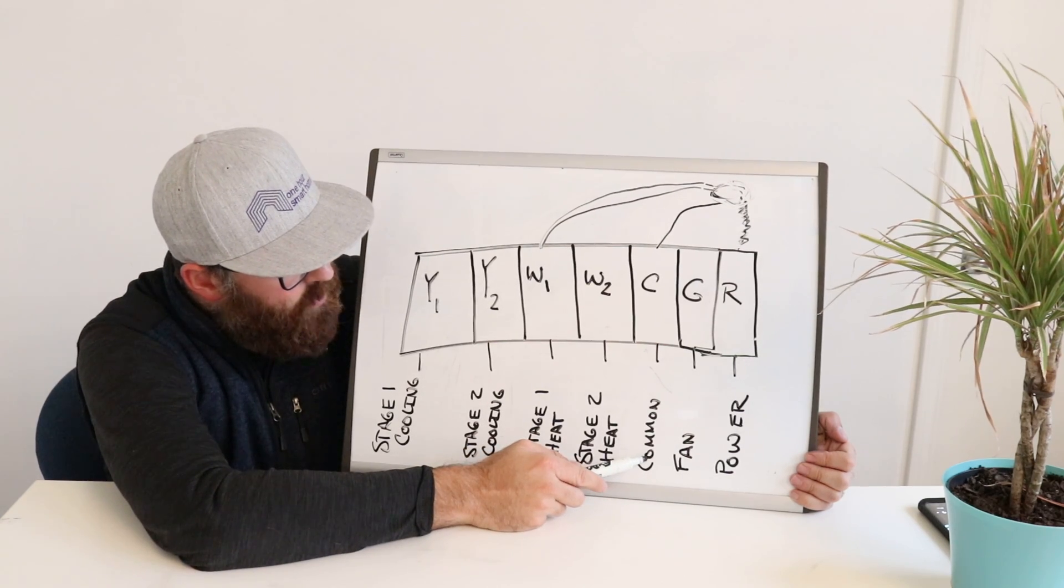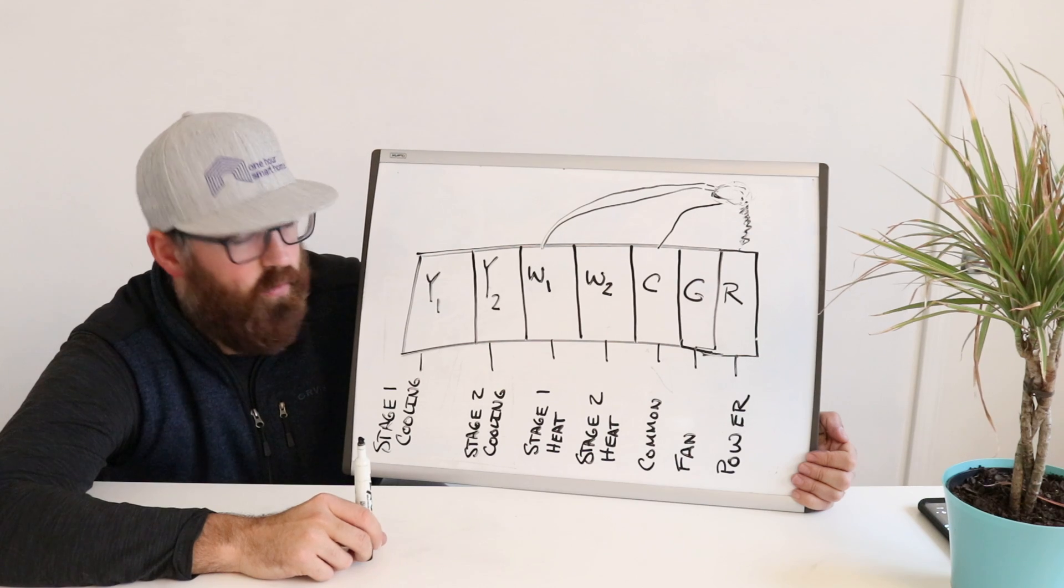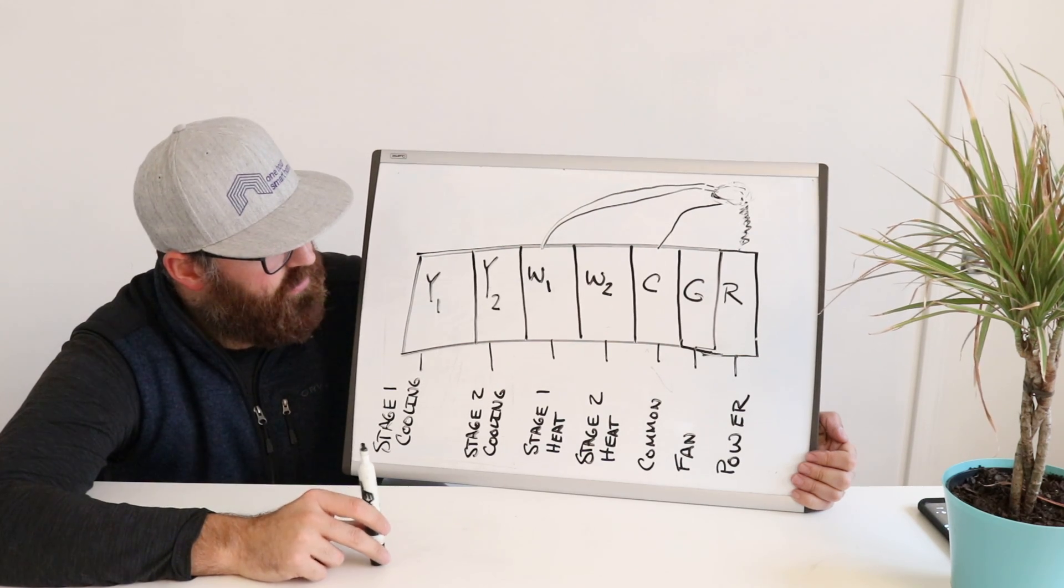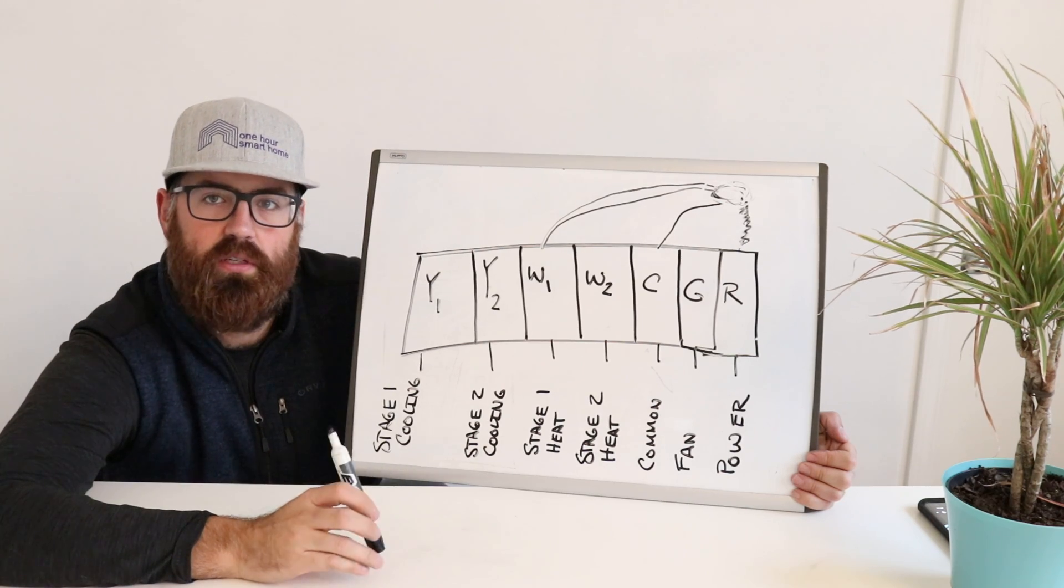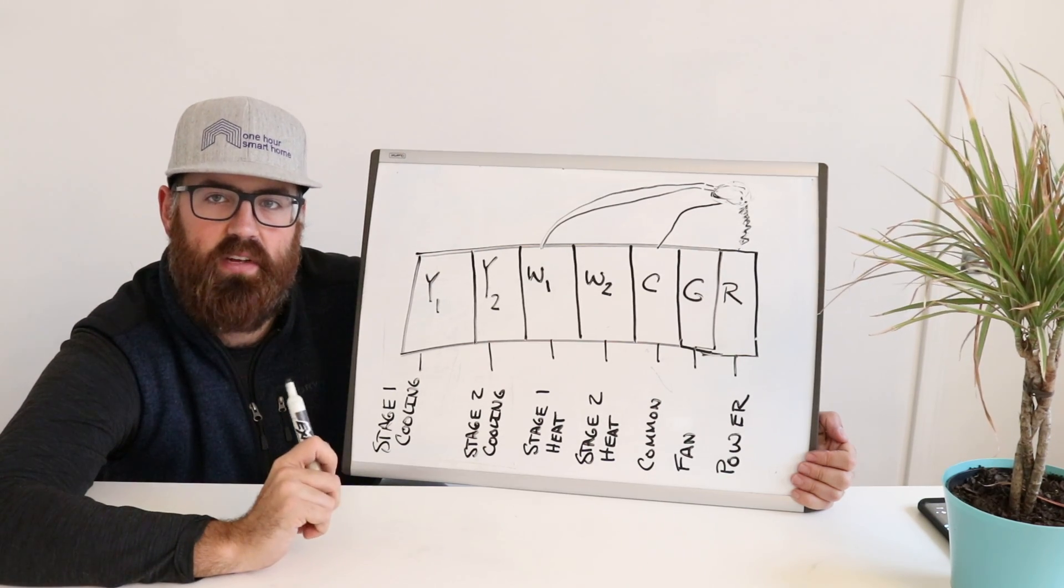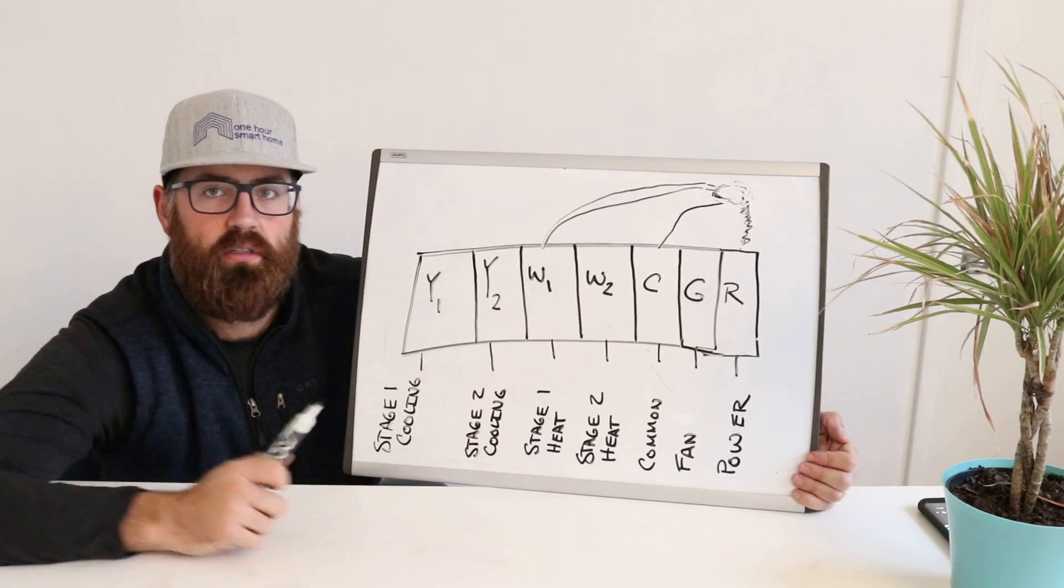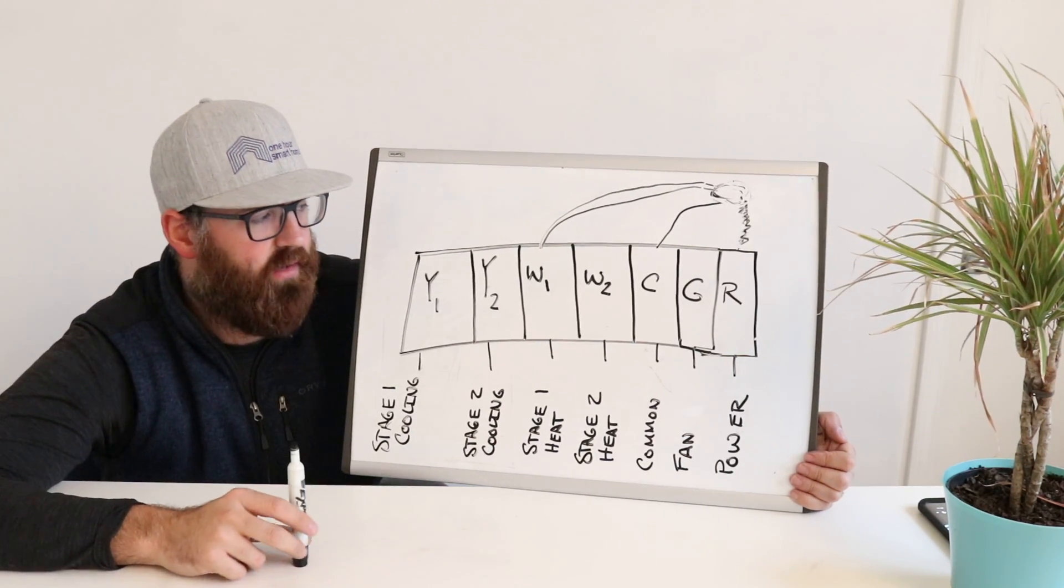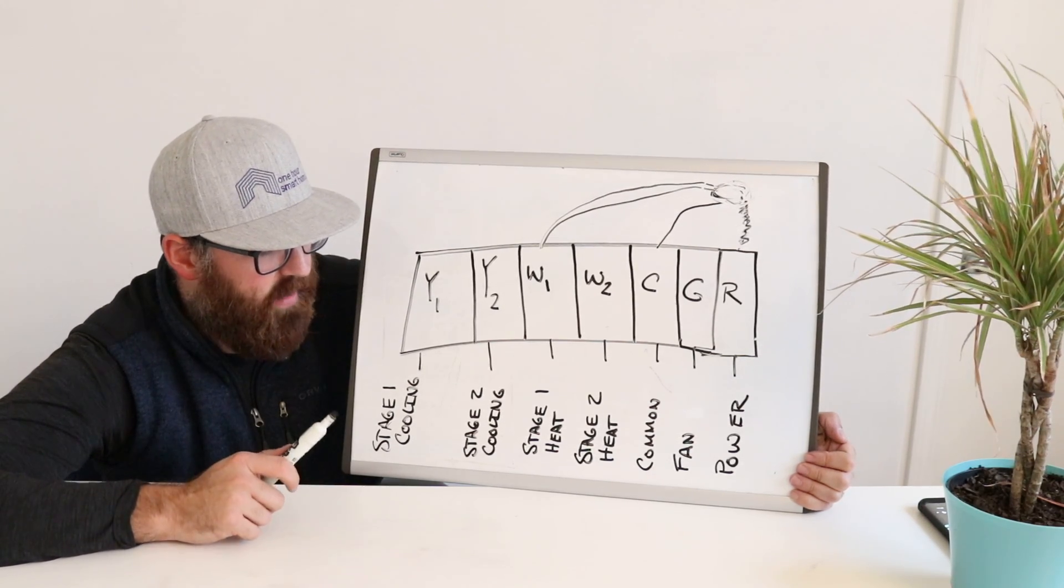So you've got your common wire, and the next thing that you have is a fan wire, G. So the G wire is for your fan, and basically what that allows you to do is control the fan inside your HVAC system independently without any heating or cooling. So if you just want to blow air around in your house in those moderate times of the year, you can absolutely do that with the G wire.